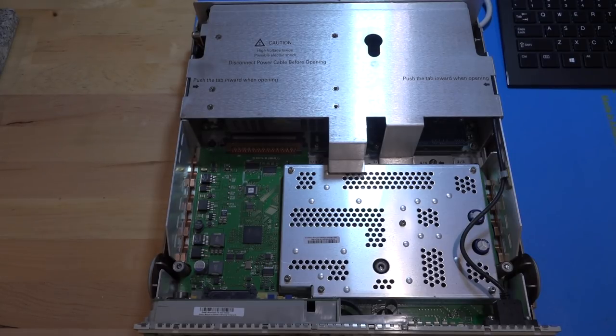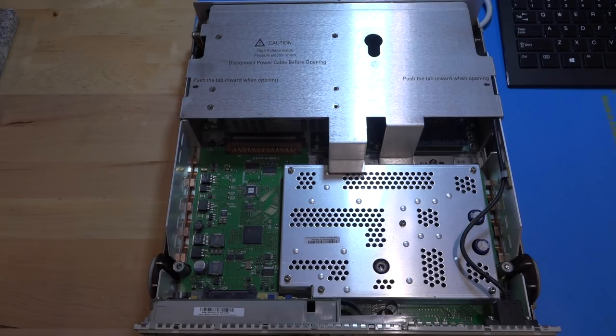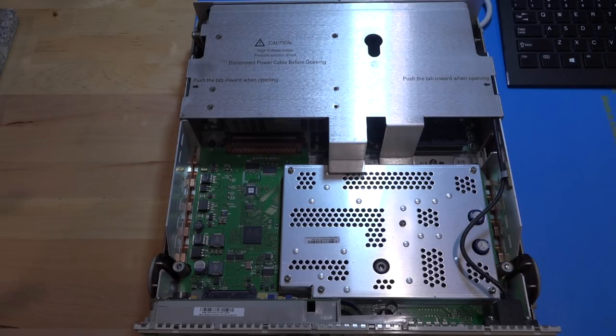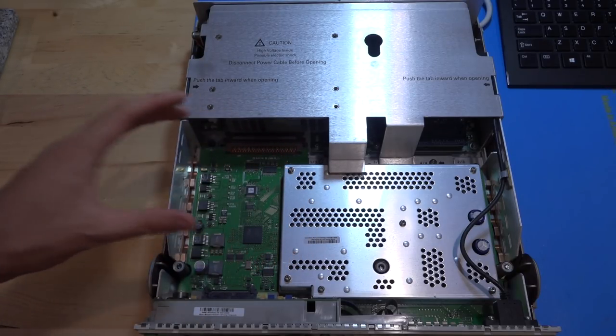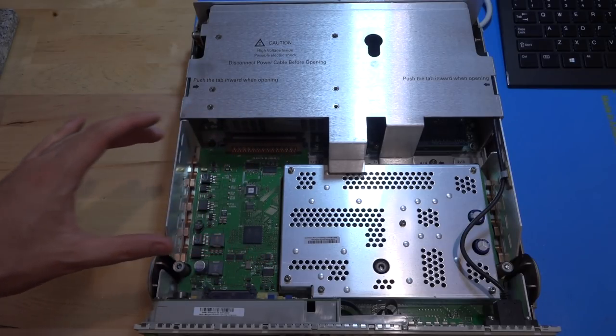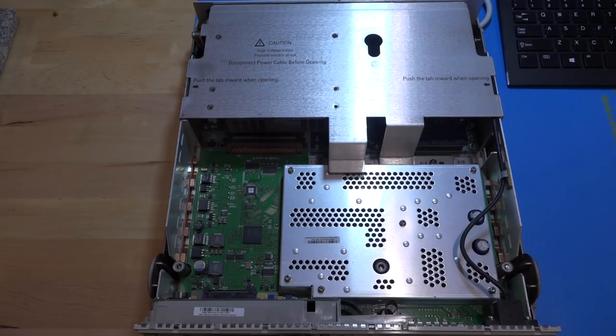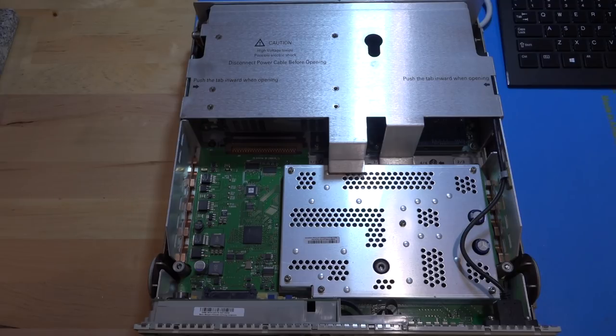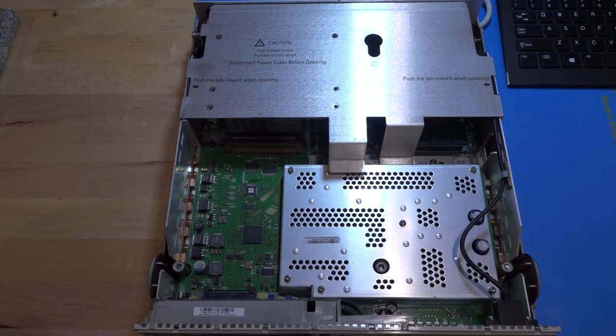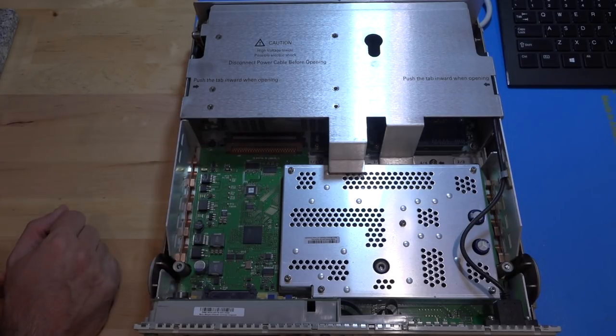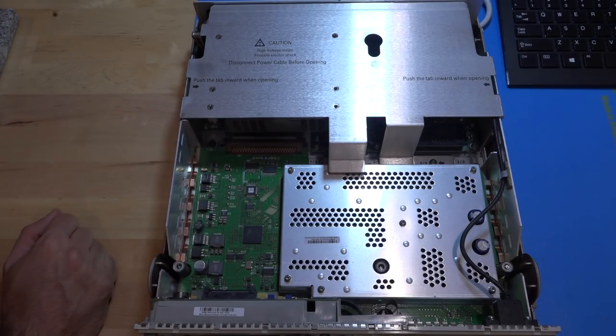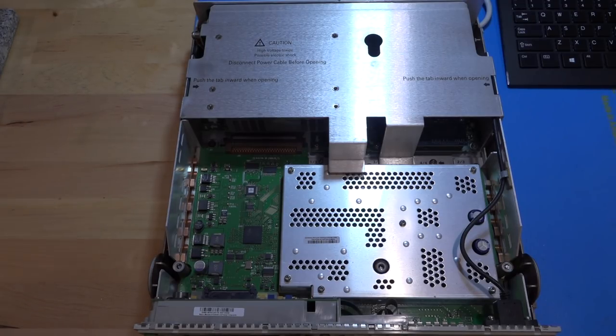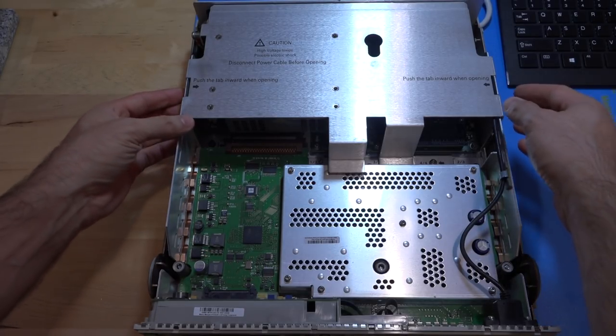So let's go ahead and see what we can do. I just opened it actually for the first time myself. So we're looking at it at the same time. Now it's pretty clear that the portion down here is all the analog. That's the angle of the waveform and digitizing the current and the voltage and finding how much phase shift is introduced, and that's how you calculate the impedance. All these sensitive circuitry is obviously hidden underneath this cage. Two little capacitors poking out. It's kind of funny looking over there. So there's a USB cable coming to the front. And I see over here Xilinx. I can't see it from my angle. It's a Spartan. So there's obviously some logic board here. So perhaps the FPGA is corrupted, and that's going to be pretty difficult to fix, unfortunately.